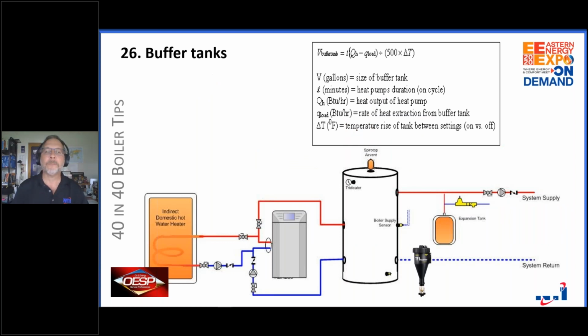Buffer tanks: a lot of people love them. I like them in certain installations, not all installations. A buffer tank not only separates your system so that your system can have one flow and the boiler can have one flow, but also gives a place for any dirt and sediment to settle out, the air to come out of solution, and allow a place for your boiler to be able to run for at least a 10-minute cycle so that it's not always going on and off, or what we call short cycling. There's a little formula at the top on how to size a buffer tank.